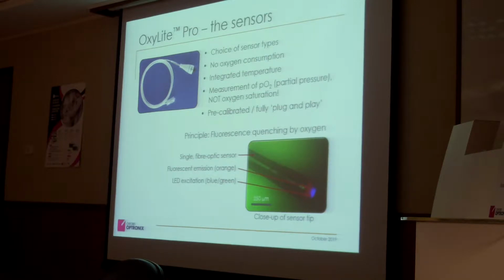We do have various types of sensors. The technology is not like the old conventional Clark-type electrodes, where you consume oxygen while you're taking a measurement. In this case, the oxygen will diffuse into the tip and out again and make an equilibrium with the surrounding tissue area. And it does not consume oxygen while it's doing it. It just makes an equilibrium.